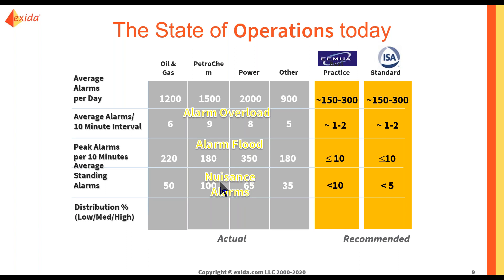Another nuisance is standing alarms — alarms that remain active for days or even years. I saw one in a Pennsylvania oil refinery that had been standing for 400 days and nobody, not even the control engineer, knew what it was for. These standing alarms take up space in the alarm list and serve no purpose. The ISA standard advises limiting standing alarms to fewer than five.